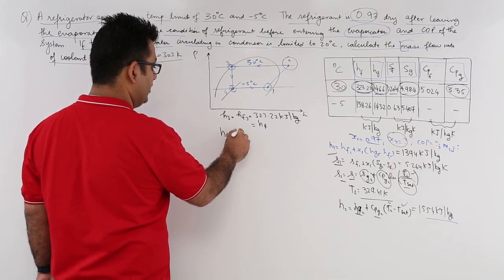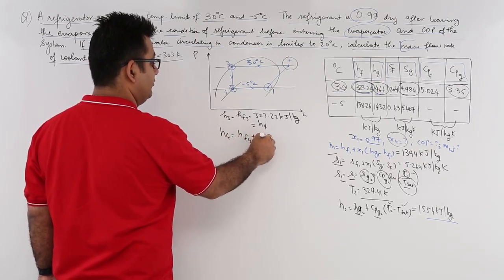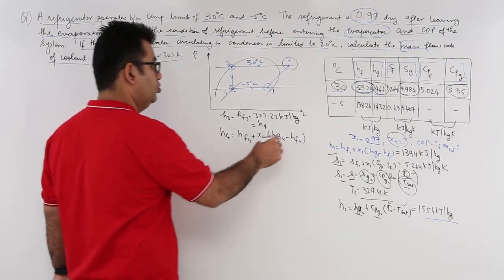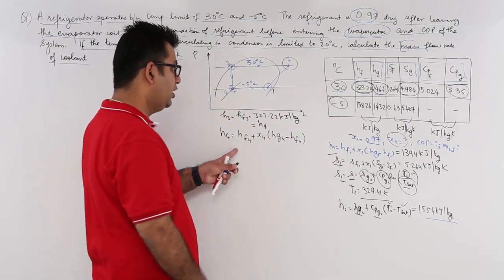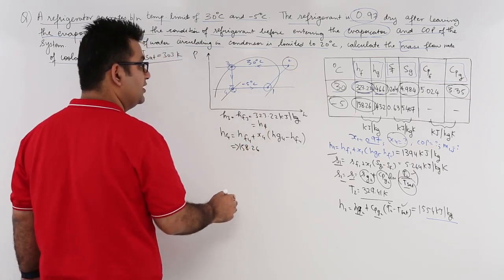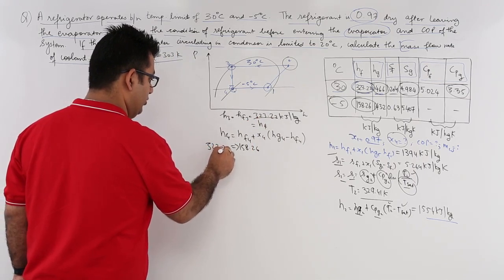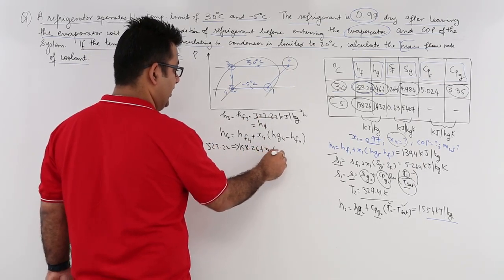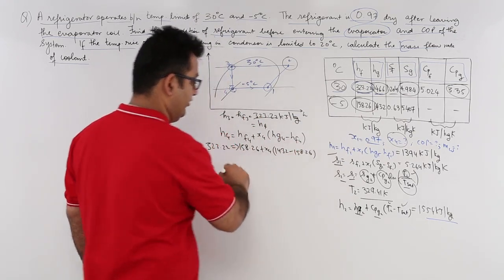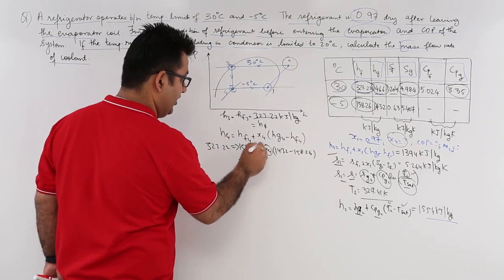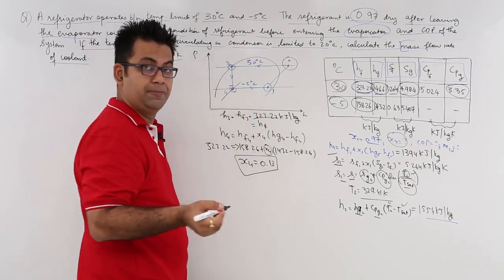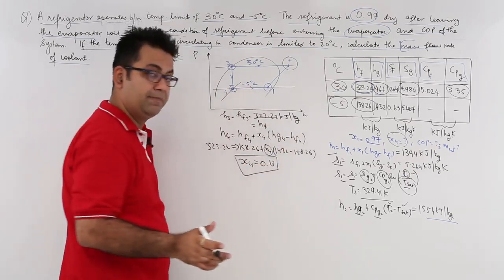To find x4: H4 = HF4 + x4 · (HG4 − HF4), where this corresponds to the temperature of minus 5°C. HF4 = 158.26 kJ/kg, HG4 = 1432 kJ/kg, and H4 = 323.22 kJ/kg. Solving for x4 gives x4 ≈ 0.13. So the refrigerant is 13% dry before entering the evaporator.